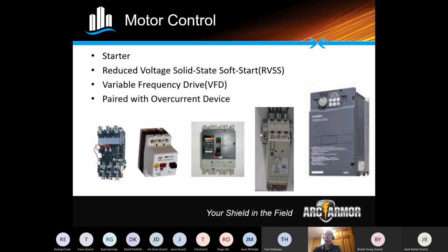The next item over here is what we would call an RVSS, or a solid state starter, or soft starter. Many of you may have these installed in your panel. They're really designed to prevent inrush on startup. Once they have started up, they can function as just a normal across-the-line starter. A lot of times these devices will have what they call a bypass contactor on them. So they'll use the solid state portion to start the motor to protect and reduce the inrush. Once it's up to speed, it will switch to what they call just across the line with a bypass contactor.